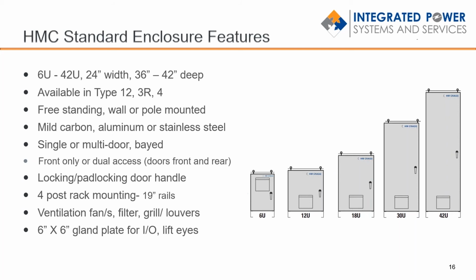So 6 through 42U will always be 24 inches wide, so they're going to look a lot like an IT enclosure. It'll fit 4-post rails on the inside, and they'll fit any type of rack-mounted gear, whether that's a UPS or a switch the customer may own, like a Cisco switch. As long as it will fit on those standard rails, we can house it inside of this enclosure. Just think of these enclosures as the industrial version of an IT enclosure, because form, fit, and function, it is the same as the IT, but it has the UL ratings. Available in type 12, 3R, and 4. Freestanding, we can do some wall mount or pole mounted as well. It can be done in mild carbon, or in aluminum and stainless, as I mentioned, if you want that X rating. It can be single or multi-door, or could even be bayed.